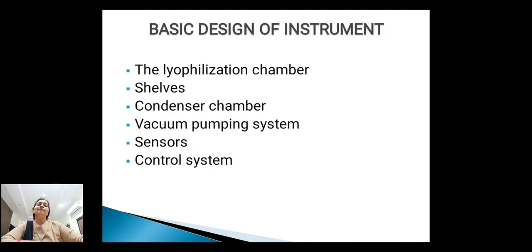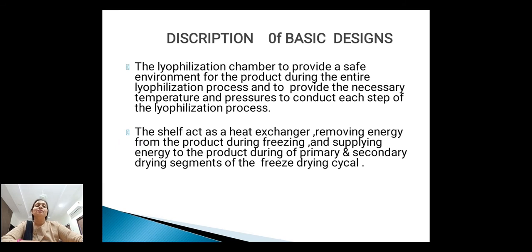Basic design of the instrument or lyophilizer. The components are: the lyophilization chamber, the shelf, condenser chamber, vacuum pumping system, and sensor and control system. The lyophilization chamber provides a safe environment for the product during the entire lyophilization process and provides the necessary temperature and pressure to conduct each step.